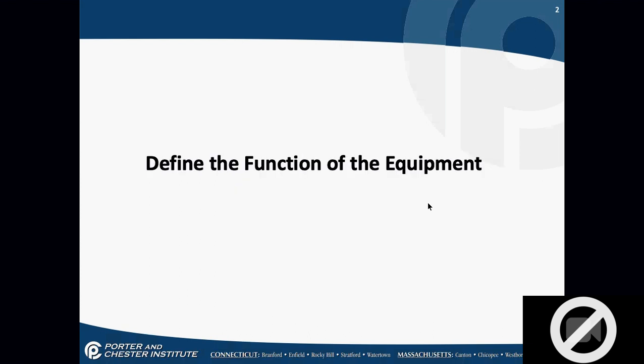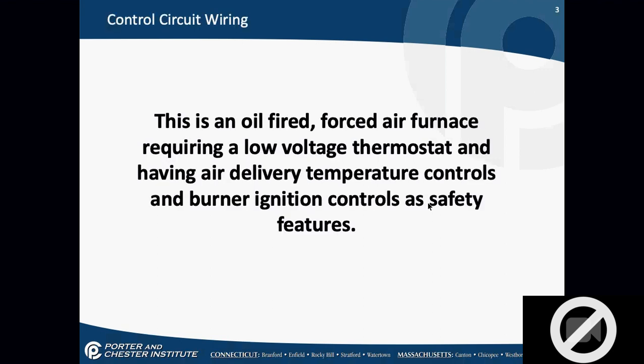The first thing we do on any control circuit, and I'm talking operating and safety controls, and this is not just oil, is look at what the function of the equipment should be. What are we doing with the equipment? What's our end goal? In this example, I'm looking at an oil-fired forced air furnace that has a low voltage thermostat, air delivery temperature controls, so we know the temperature of the air going into the space, and burner ignition controls as a safety feature.